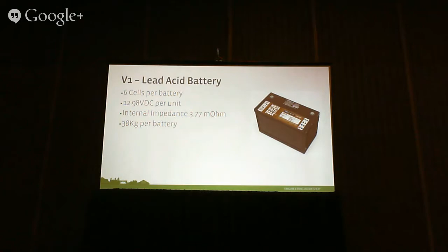So our use case for the 90 seconds, as we've been talking about, is in 2 cases really. One is when the AC outage happens. We're on the main AC, outage happens, AC goes away. The battery kicks in until the AC generator turns on. We need about 20 to 30 seconds, and then we put some forgiveness time in there and make it 90 seconds just in case.